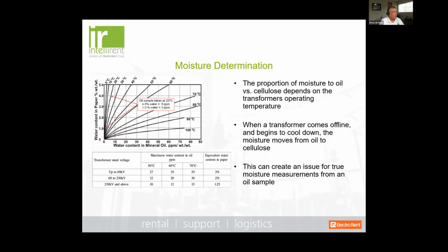So what is allowable? Well, the proportion of moisture to oil versus cellulose greatly depends on operating temperature. And this is one of the problems that we have with measuring moisture during a dissolved gas analysis. Now, the laboratories do an excellent job at measuring what they have in their possession, and using equilibrium curves if you've recorded the oil temperature at the time of taking the sample. But remember this, when you take a transformer offline, the moisture moves from the oil into the insulation itself. So there's not a direct proportion of moisture in the oil versus the insulation.